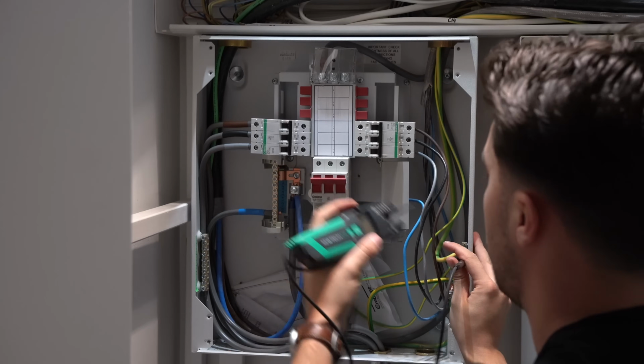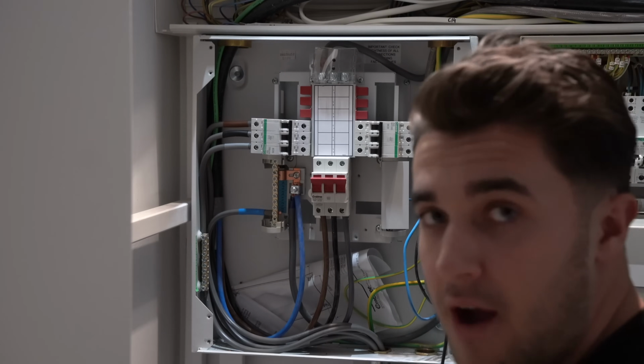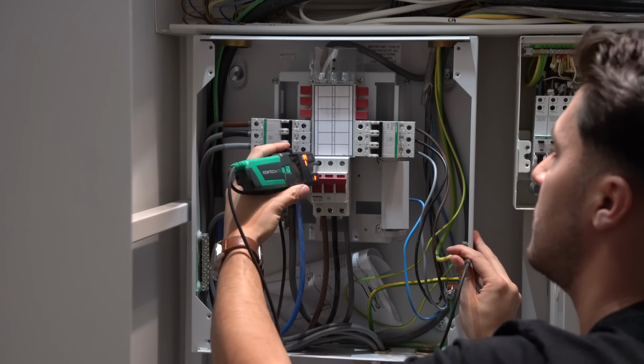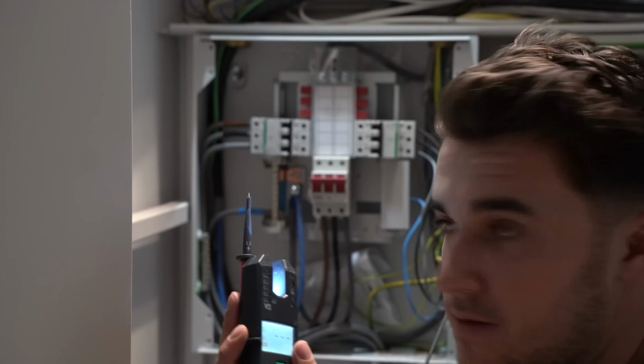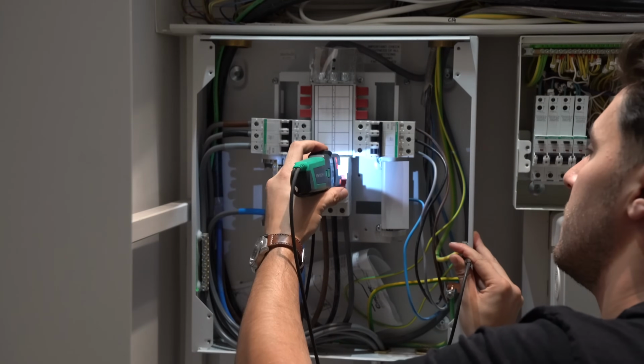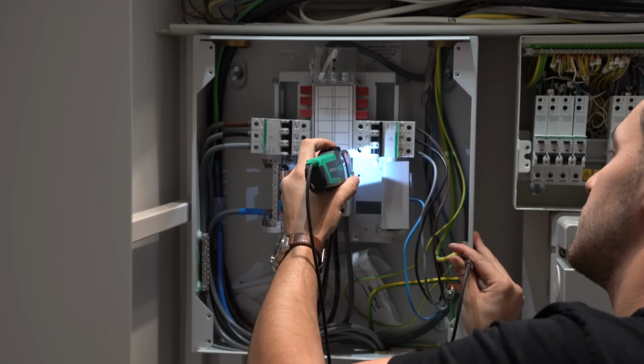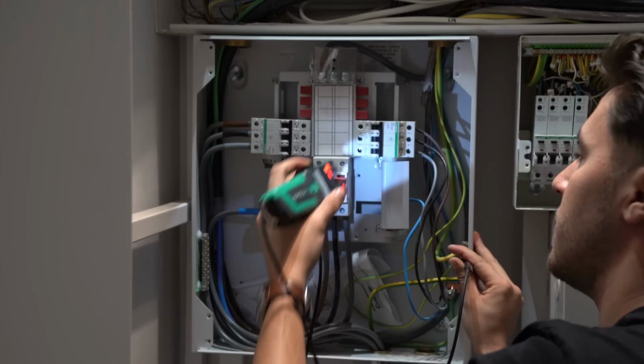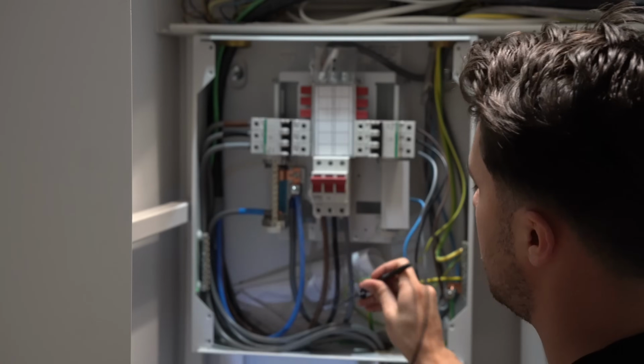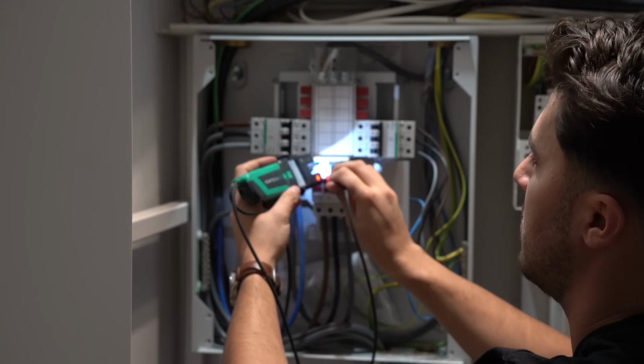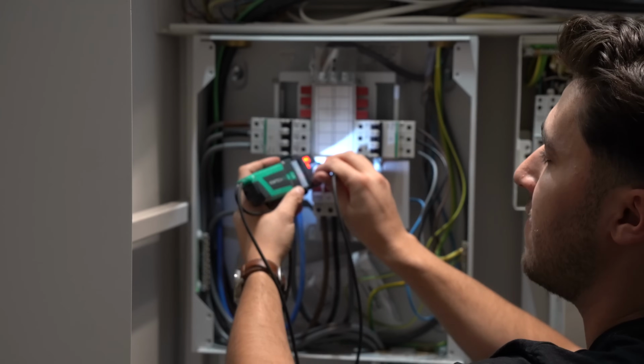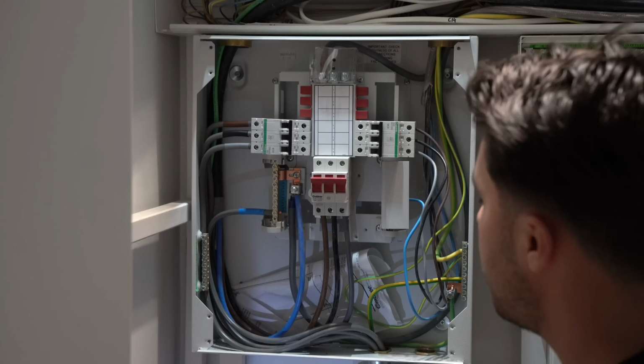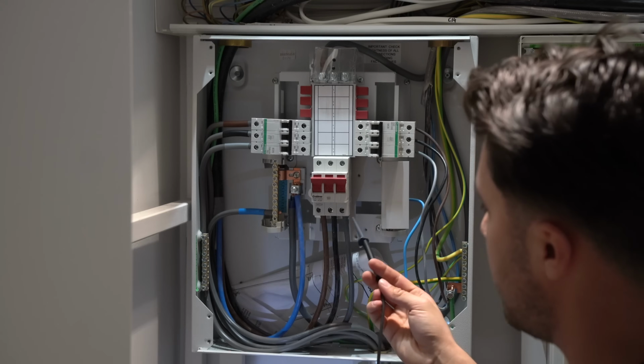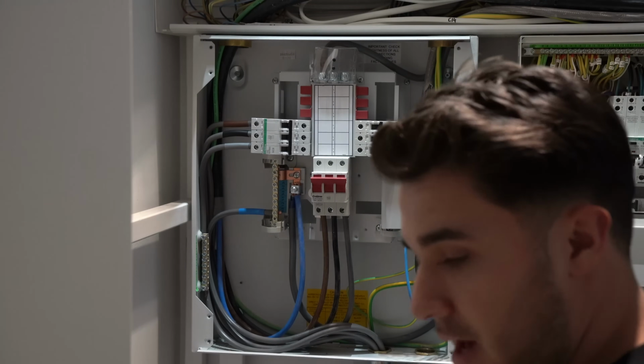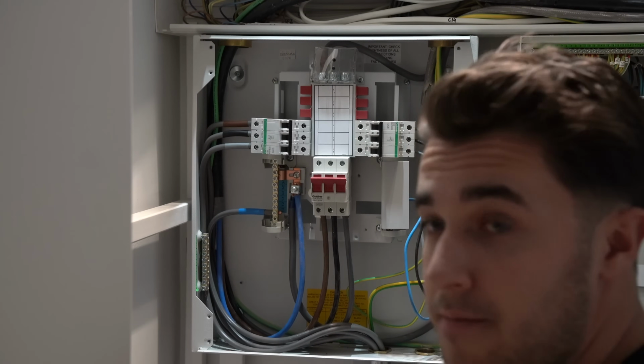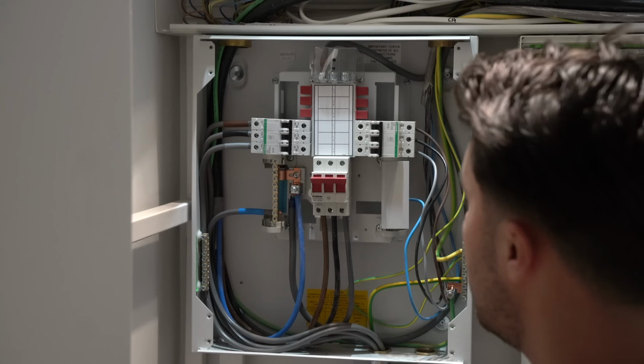If I was to measure between L1 and ground, or phase and ground, I get 242 volts. Between L2, 242 volts. L3, 245 volts. So how comes when I put them together, I'm only getting 415 and I'm not getting 460 or 690 across all the three phases? It comes down to Pythagoras' theorem and working with triangles.